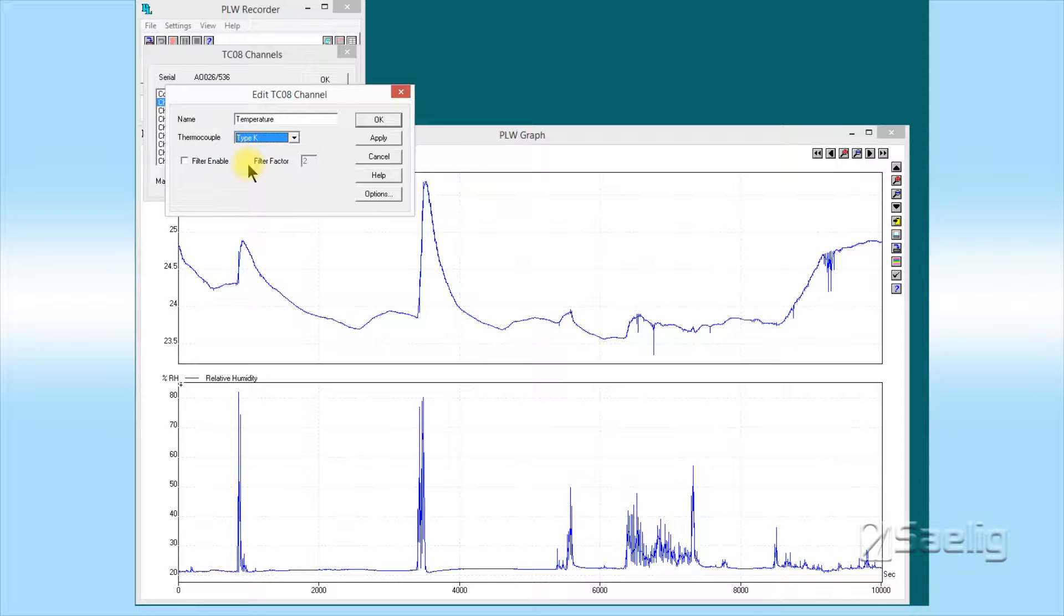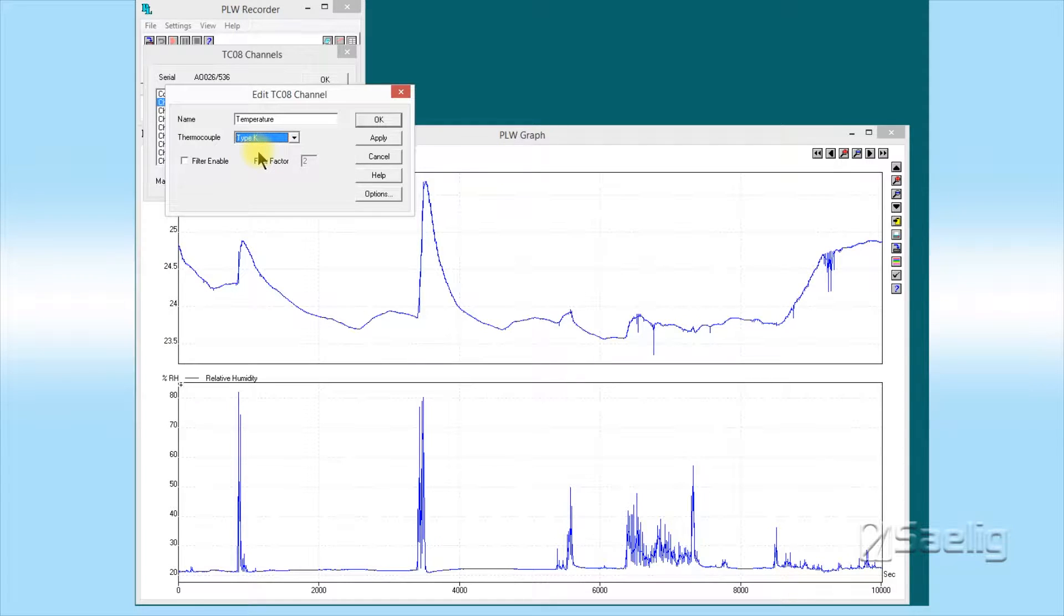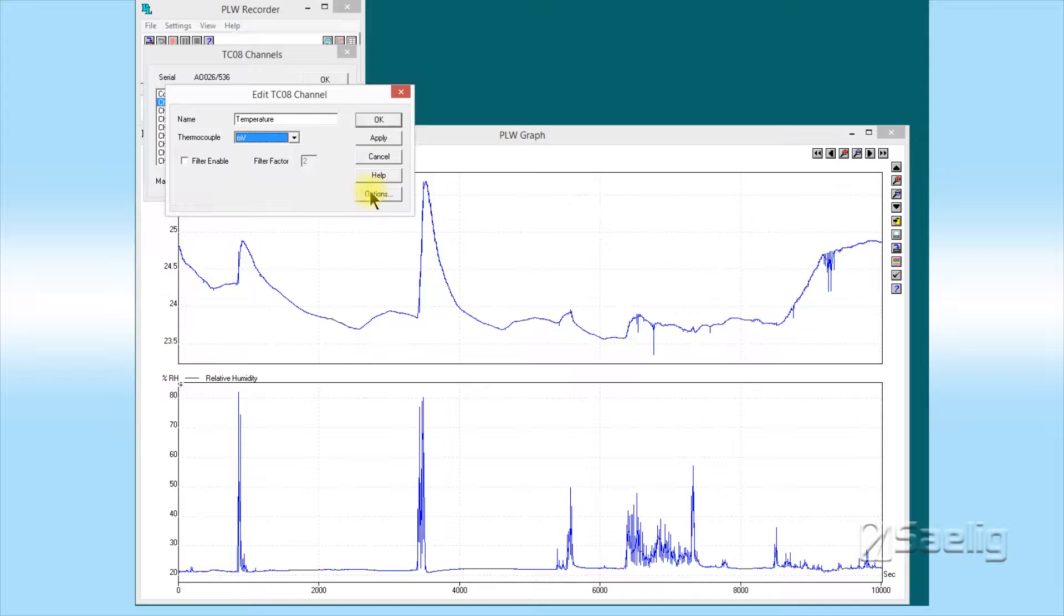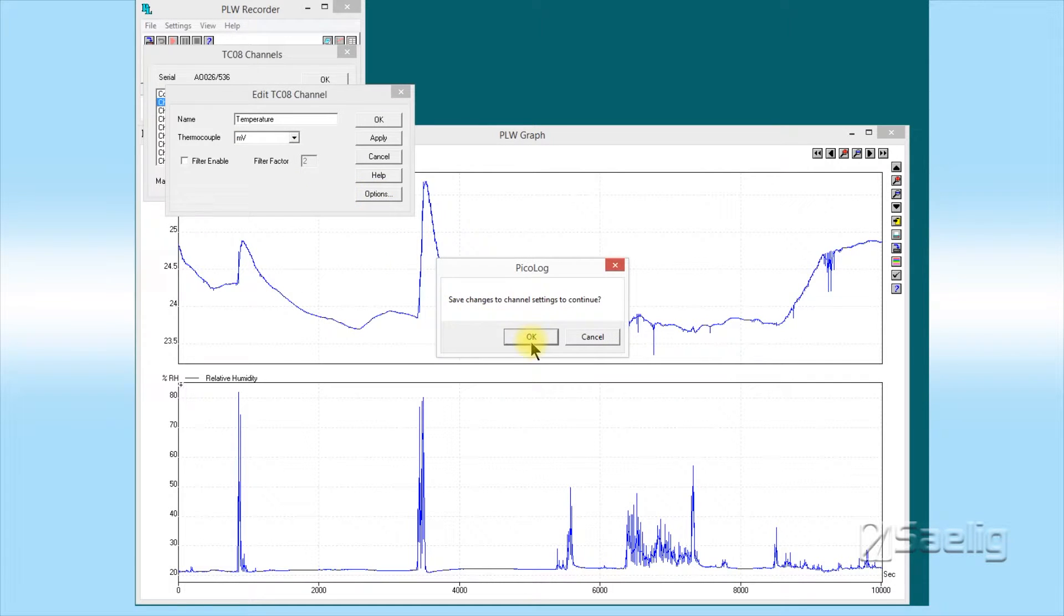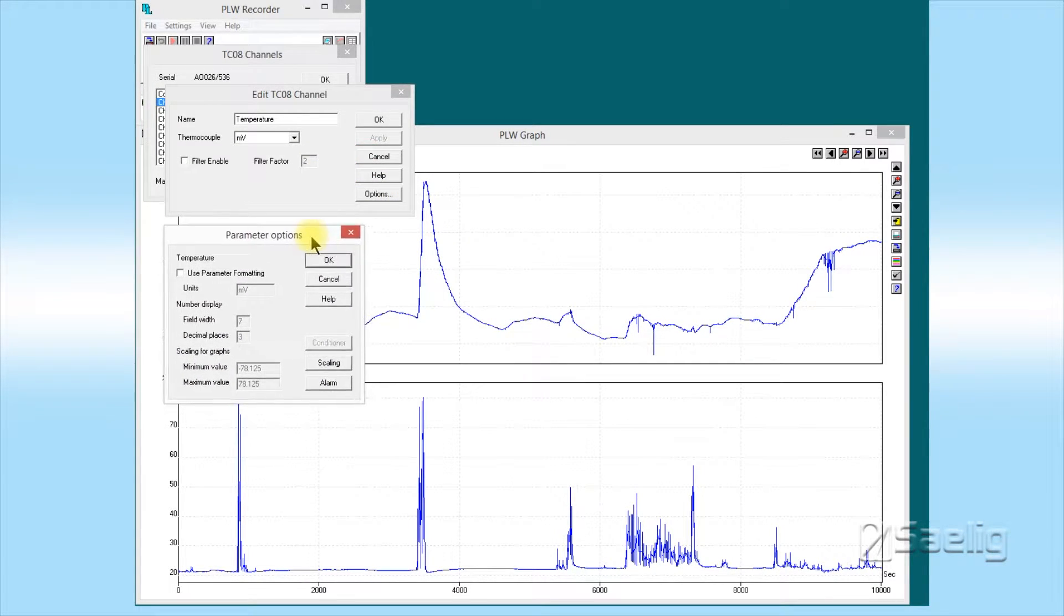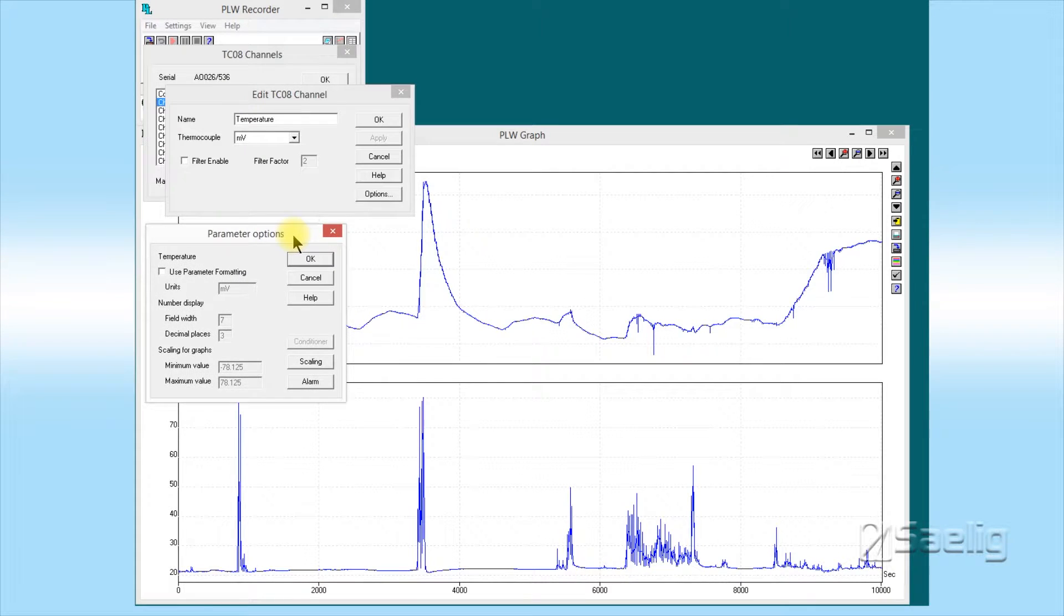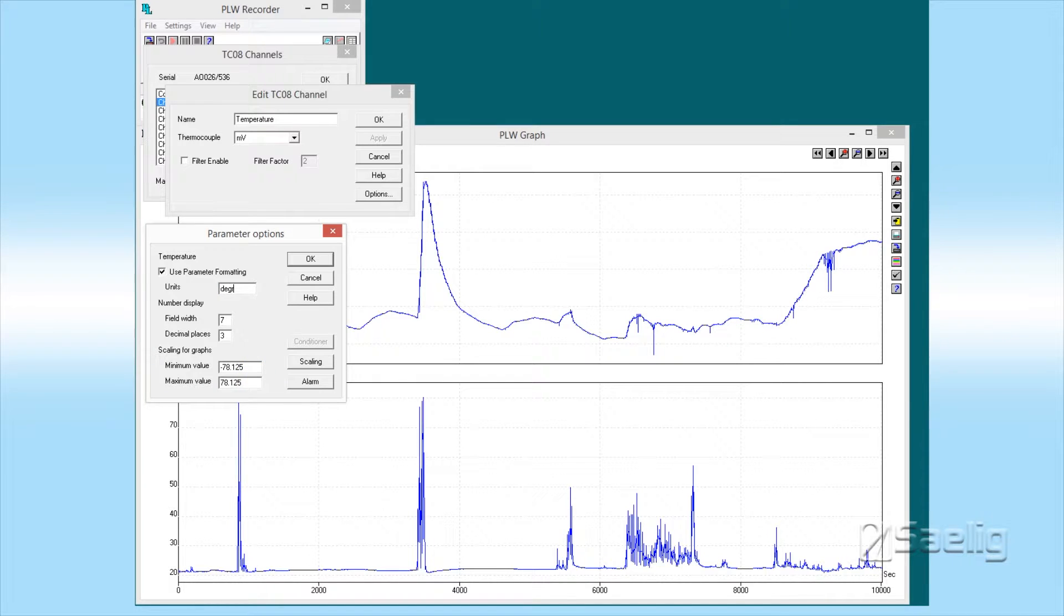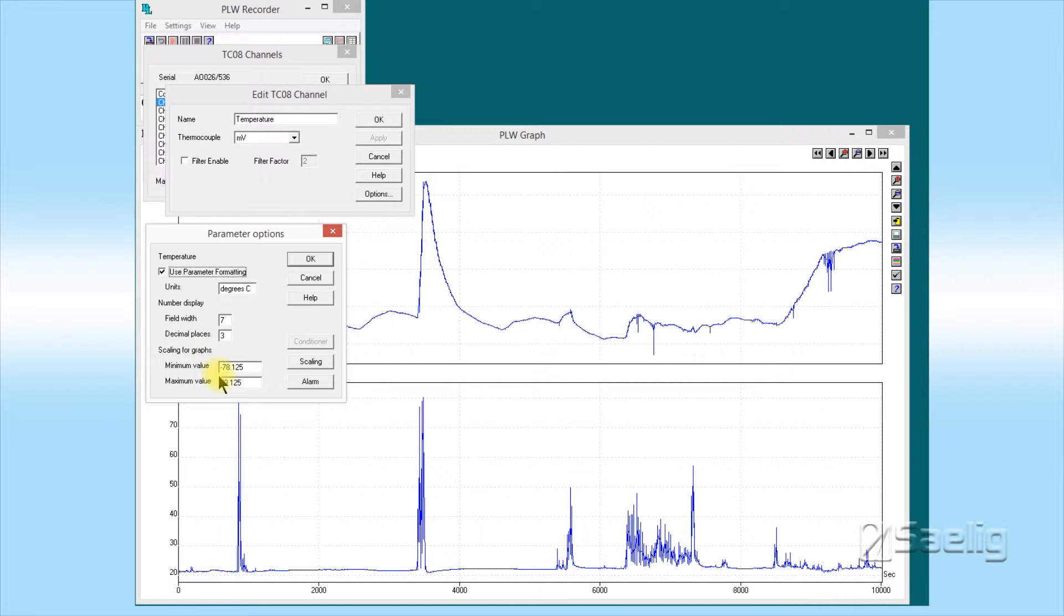Under thermocouple—this is from the instructions for the little terminal board device—we want to set this to millivolts right here. Before we apply, let's go to options and save. Now we have a new window that's open. You want to check the box for use parameter formatting. Our units are not going to be in millivolts but instead they're going to be in degrees centigrade or degrees C. Then we're going to scale for the graphs. The temperature can go from minus 10 degrees centigrade up to plus 80 degrees centigrade.